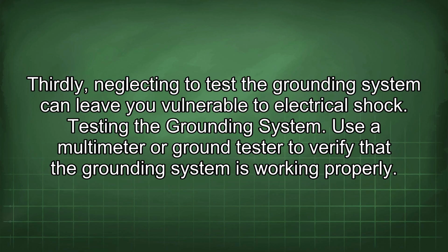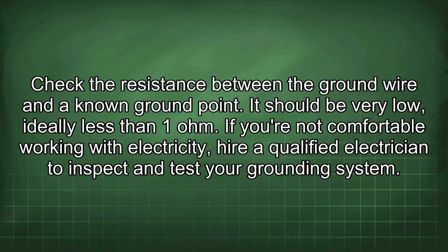Thirdly, neglecting to test the grounding system can leave you vulnerable to electrical shock. Testing the grounding system: use a multimeter or ground tester to verify that the grounding system is working properly. Check the resistance between the ground wire and a known ground point. It should be very low, ideally less than 1 ohm. If you are not comfortable working with electricity, hire a qualified electrician to inspect and test your grounding system.